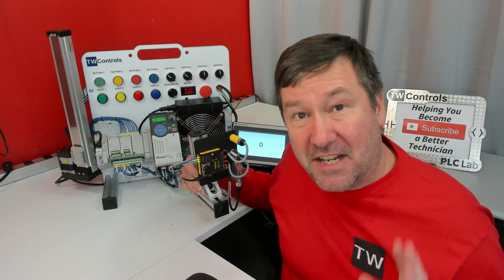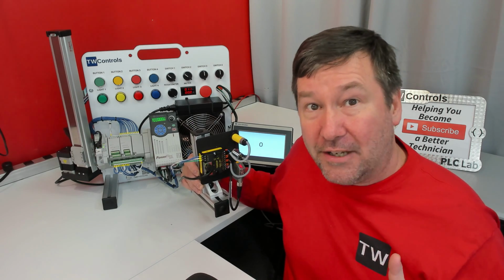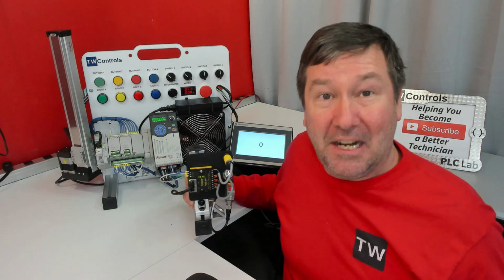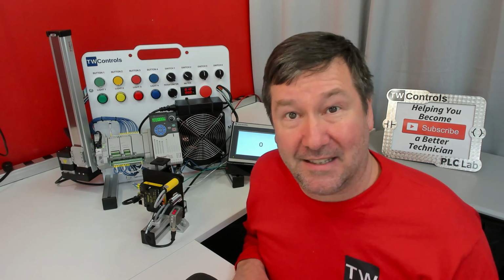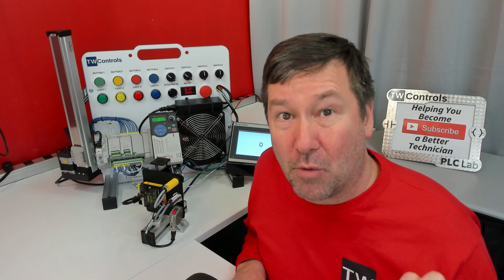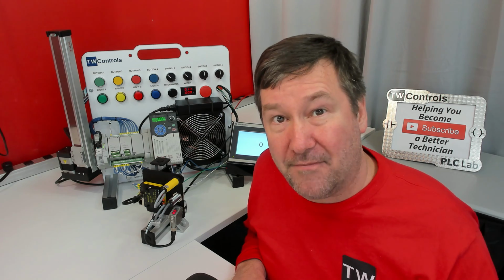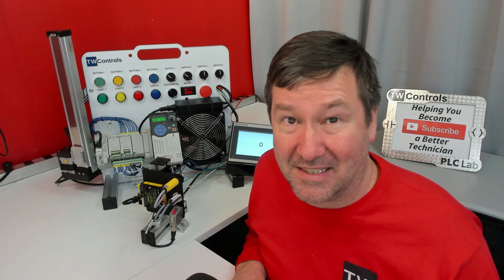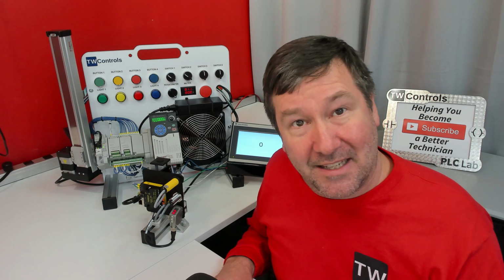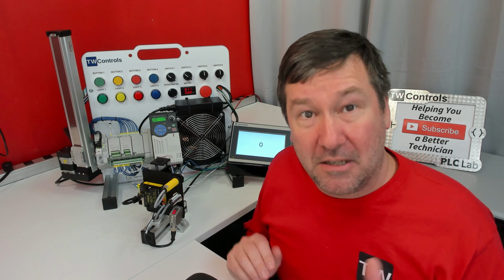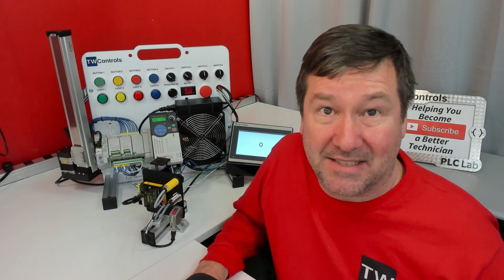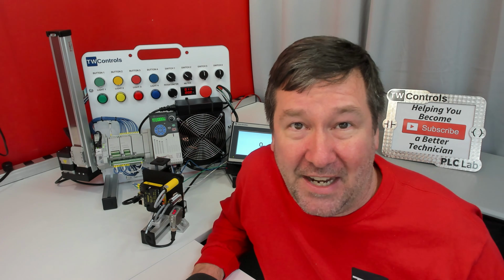In this video, I'm going to show you how to take your Turck FIN20 IO-Link module and get it communicating with a Micro850 PLC. The method I'm showing you works with a select group of Micro850 and Micro870 PLCs. We can still get data into the other ones, but for this one, we're going to be using EtherNet/IP Class 1 messaging, which is pretty much what Studio 5000 uses.